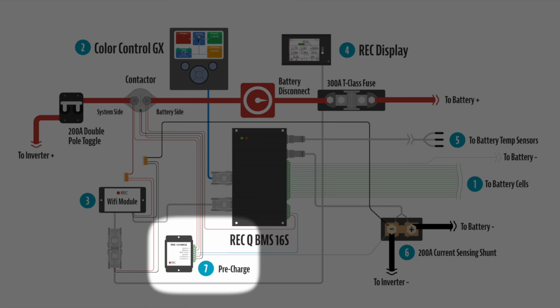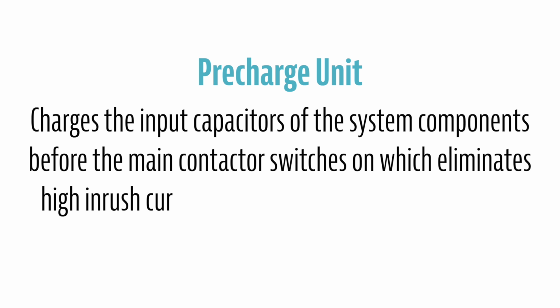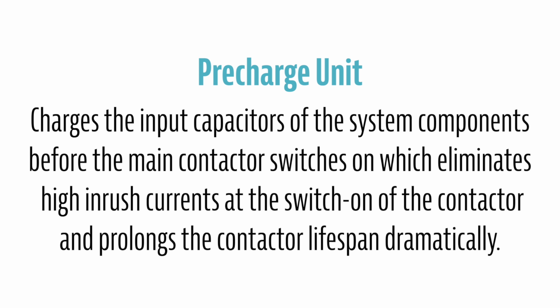Step 7: now, we mentioned the pre-charge unit above. If you're wondering exactly what this does, I'm just going to read it to you. It charges the input capacitors of the system components before the main contactor switches on, which eliminates high inrush currents at switch on of the contactor.